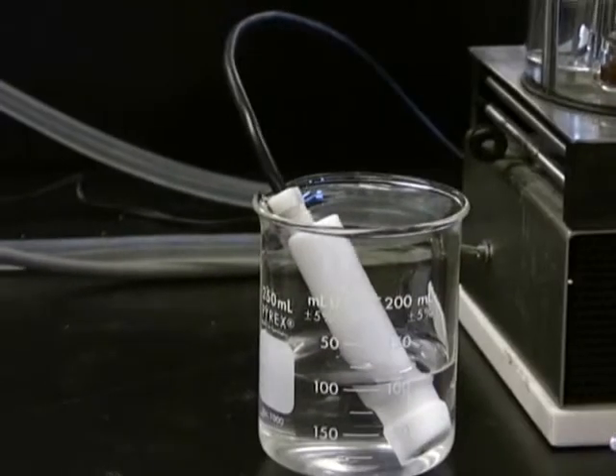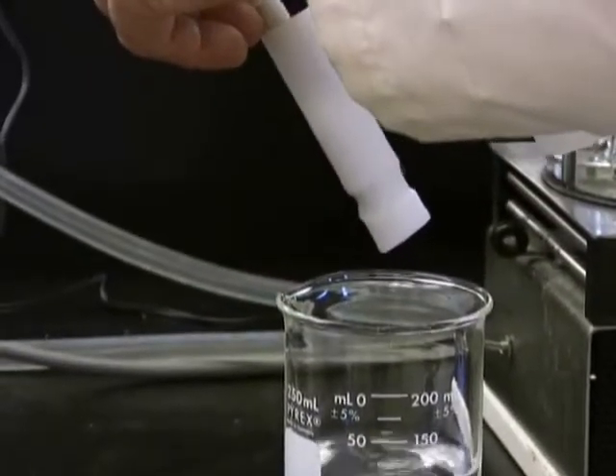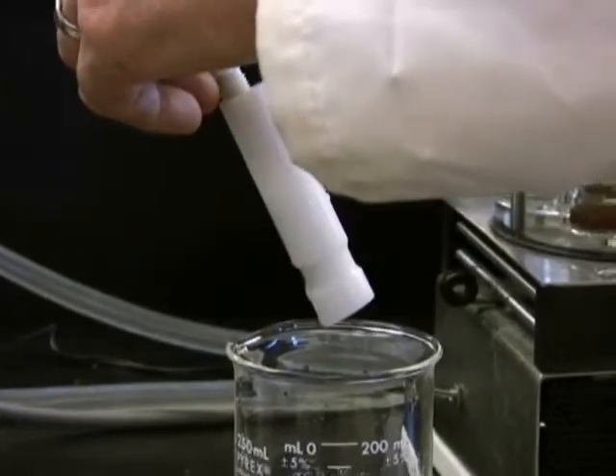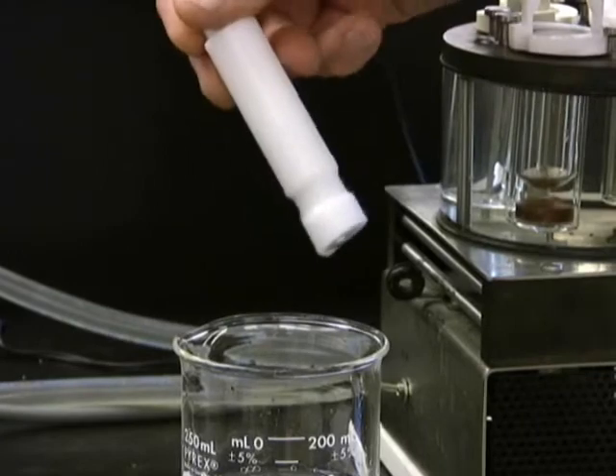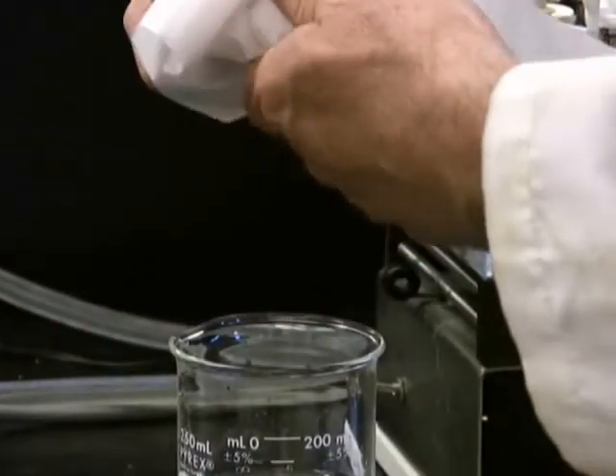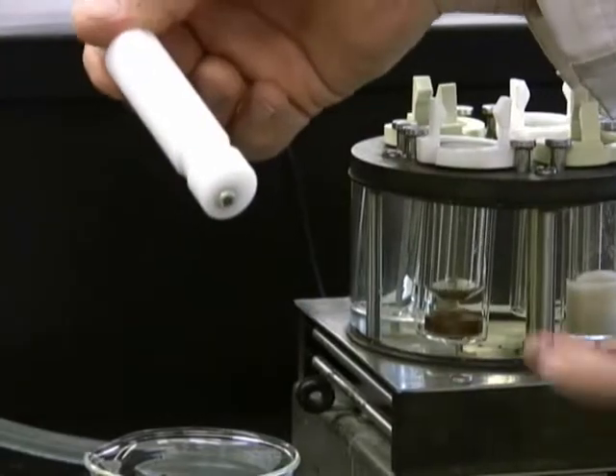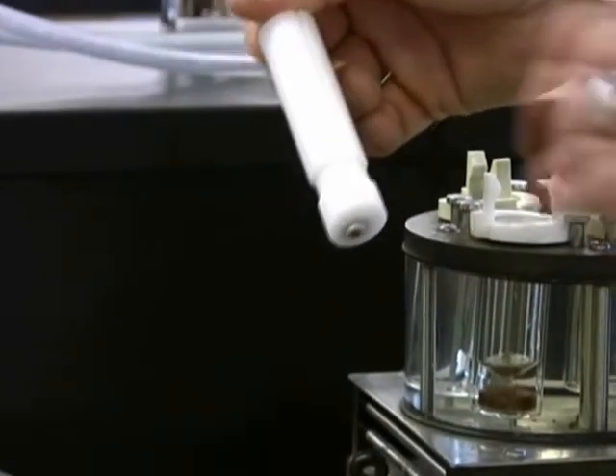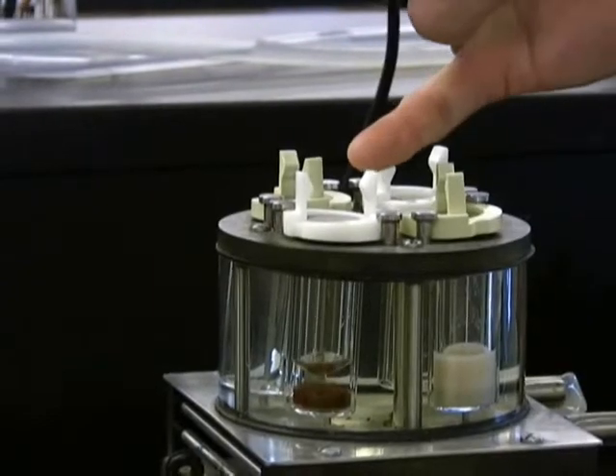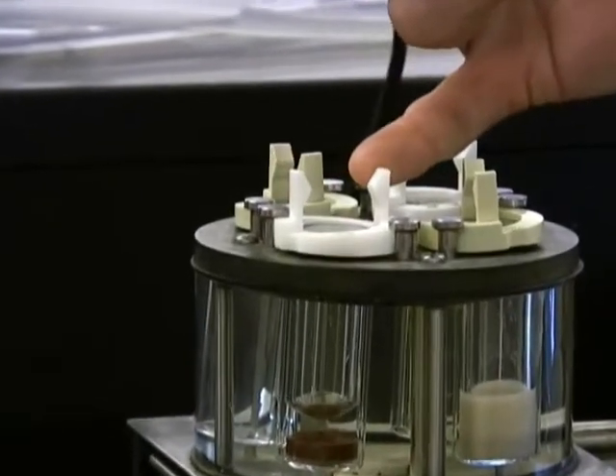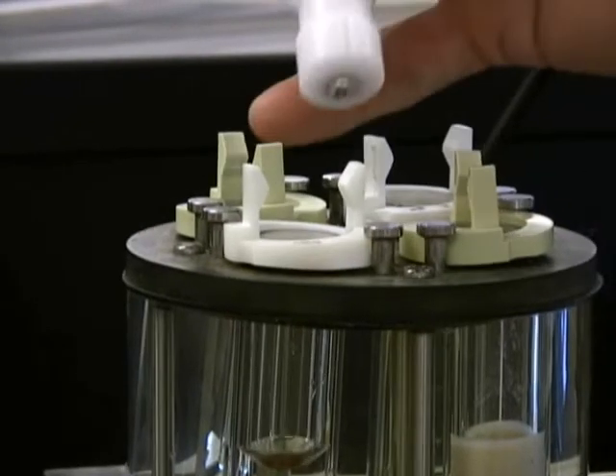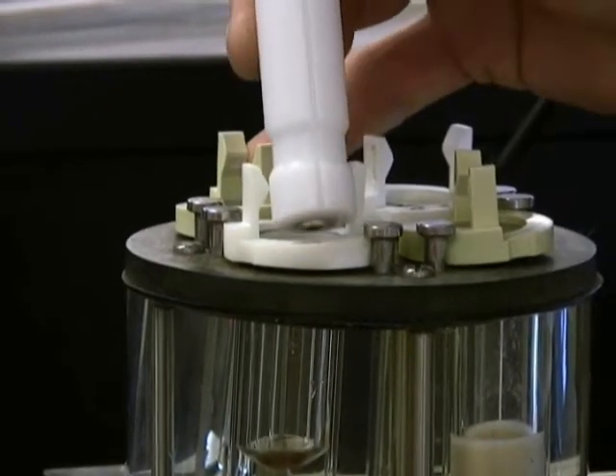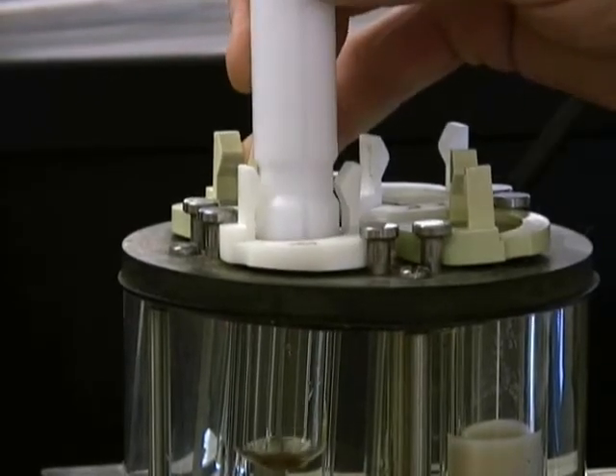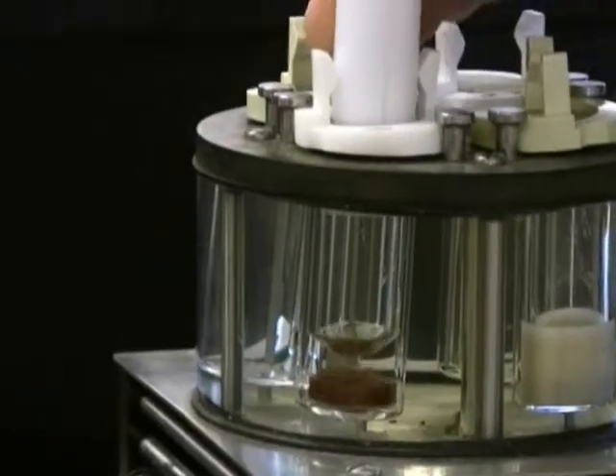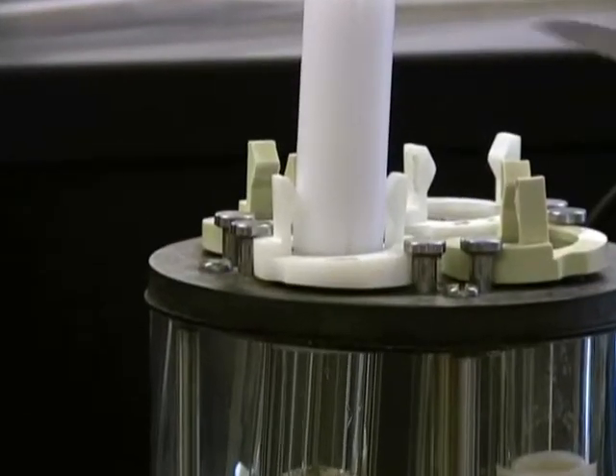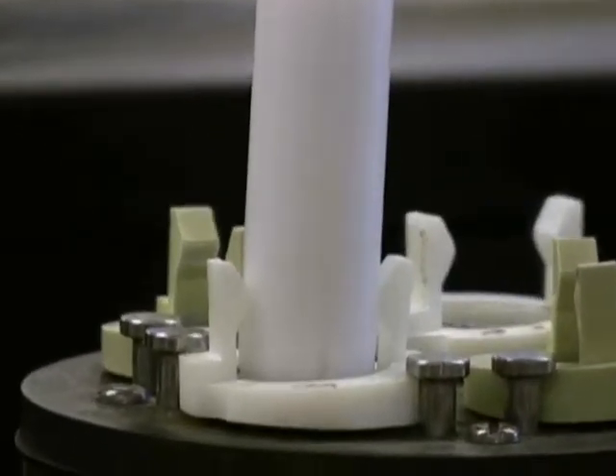So we need to rinse the probe, and then we take off the excess water using a Kleenex, but we must not touch the membrane. So you wipe the outside of the electrode, but you don't touch the membrane. Now when you put the probe in, one thing to notice is at the top we have these finger-like devices that put friction on the body of the electrode. So you rest the electrode on these fingers and then you press it in.